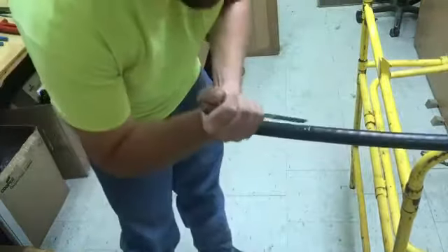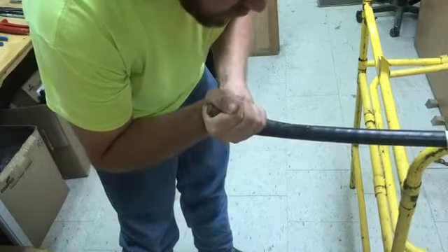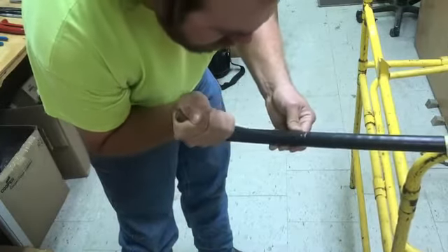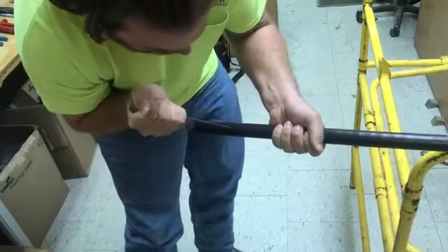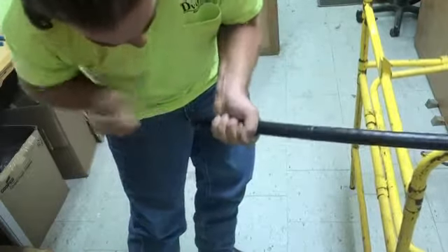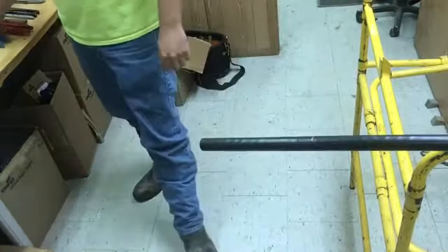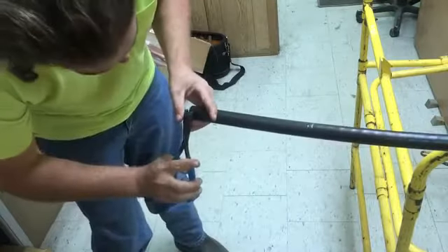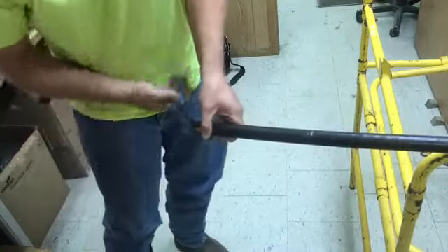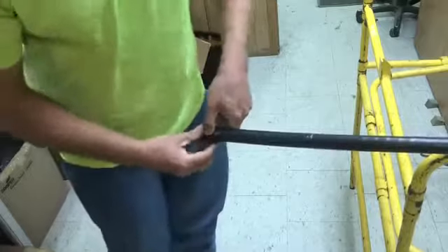The next cut made is the longitudinal outer jacket cut. It goes from the ring cut to the end of the cable. You need to be careful not to apply too much pressure to damage the underlying layers. Once the longitudinal cut is made, the duckbill pliers are used to separate the outer jacket and remove the outer jacket.